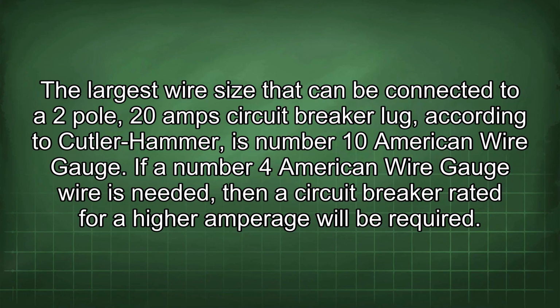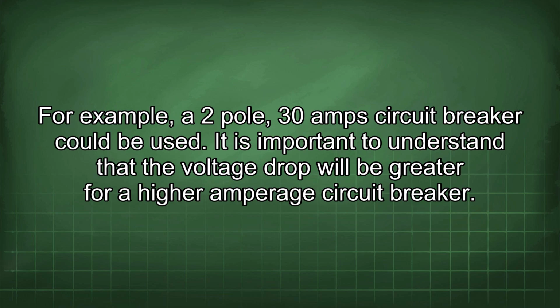The largest wire size that can be connected to a 2-pole, 20-amp circuit breaker lug, according to Cutler-Hammer, is number 10 American wire gauge. If a number 4 American wire gauge wire is needed, then a circuit breaker rated for a higher amperage will be required. For example, a 2-pole 30-amp circuit breaker could be used.